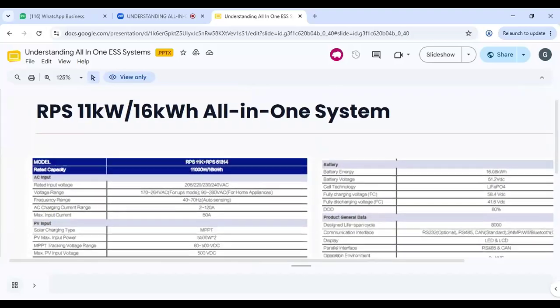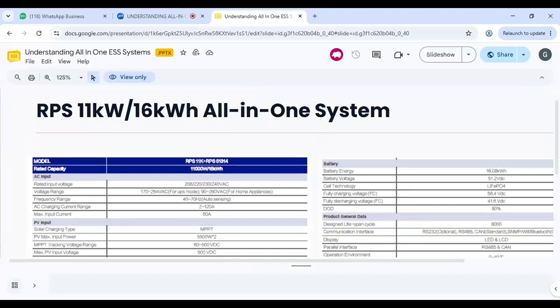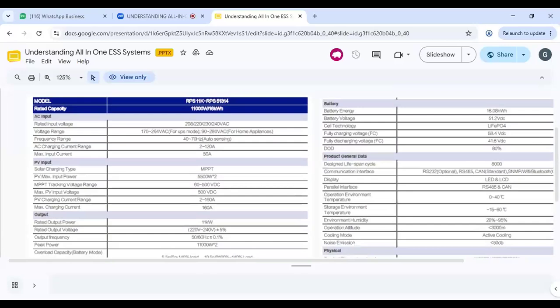Now, let's look at the RPS 11 kilowatts by 16 kilowatt hour all-in-one battery. The output voltage is the same, all other things are the same, but the charging capacity in terms of solar differs, because you can see the MPPT capacity is 5,500 watts times 2. So it has 2 inputs, 2 MPPT trackers. You can connect 2 lines of solar panels to it to be able to get more energy. It's also high voltage in terms of the solar, 60 to 500 volts.